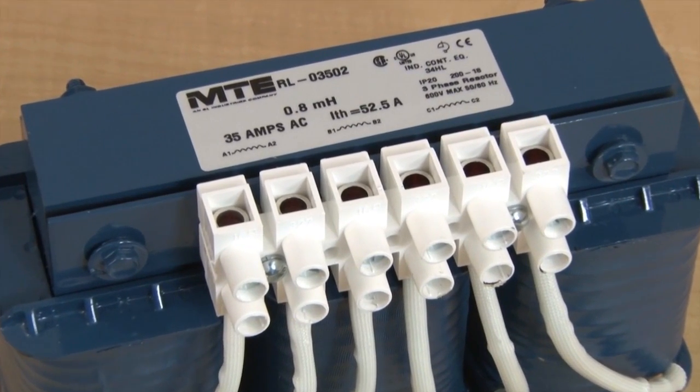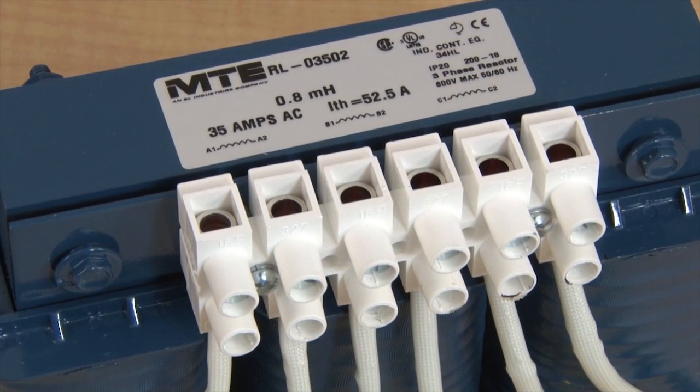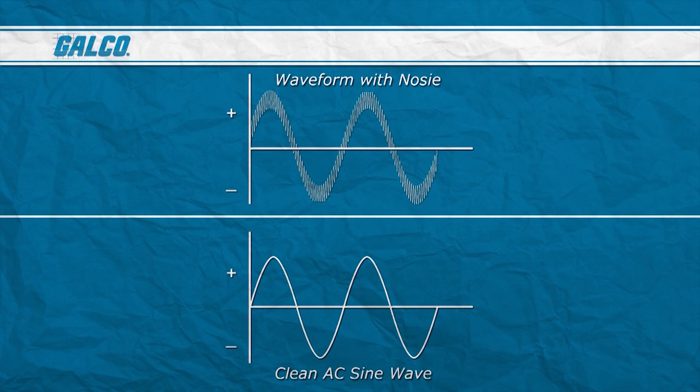The purpose of these filters is to minimize electrical noise such as voltage spikes and reduce power line distortion from VFDs. A line reactor acts not only as a current limiting device, but it also filters the waveform and attenuates electrical noise and transients associated with the system.